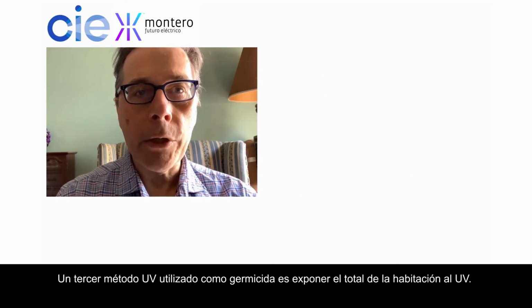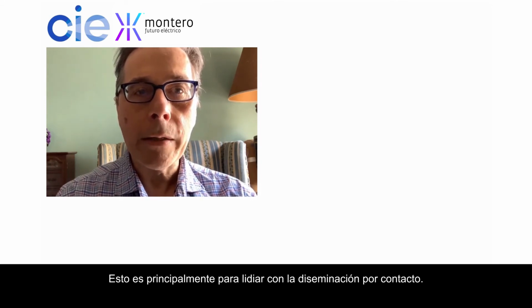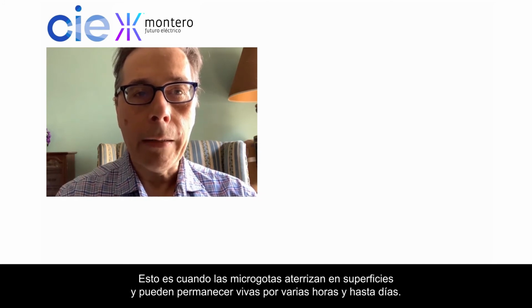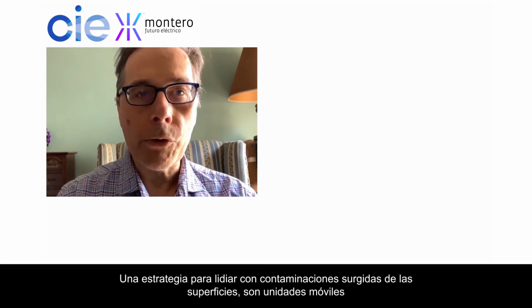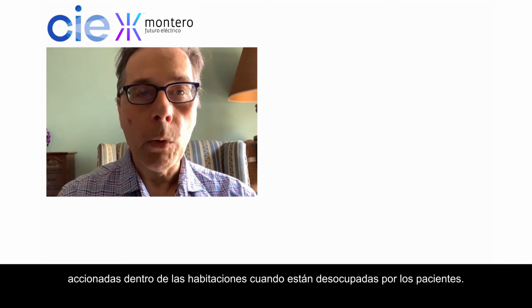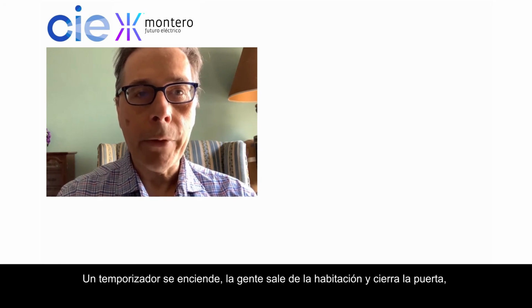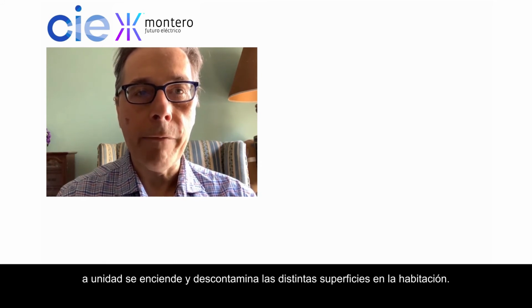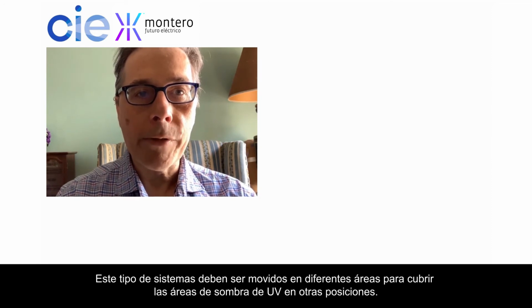A third method being used for germicidal UV is whole room UV, primarily to deal with contact spread, where droplets land on surfaces and can stay alive for many hours and days. Strategies for dealing with these surface-borne contaminations include mobile units rolled into a patient's room when it is unoccupied. A timer is switched on, people exit the room and close the door, and the unit decontaminates the various surfaces in the room. These systems have to be moved to different areas to overcome the various shadowing effects of UV.